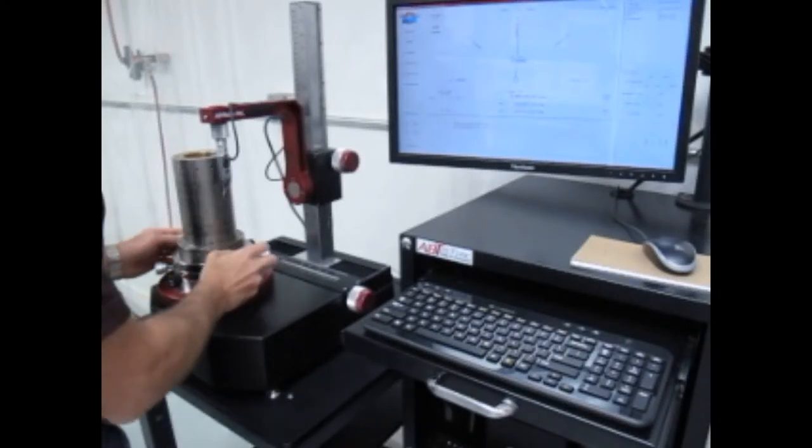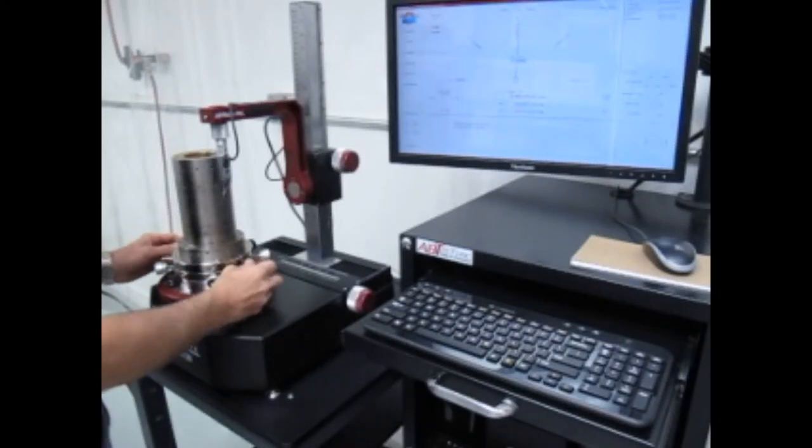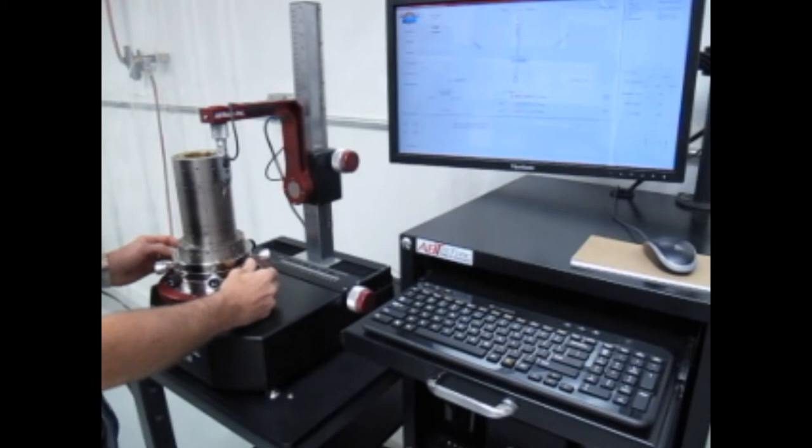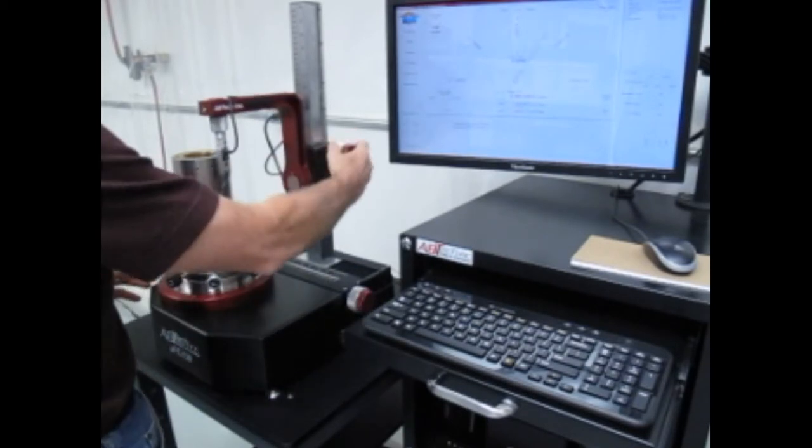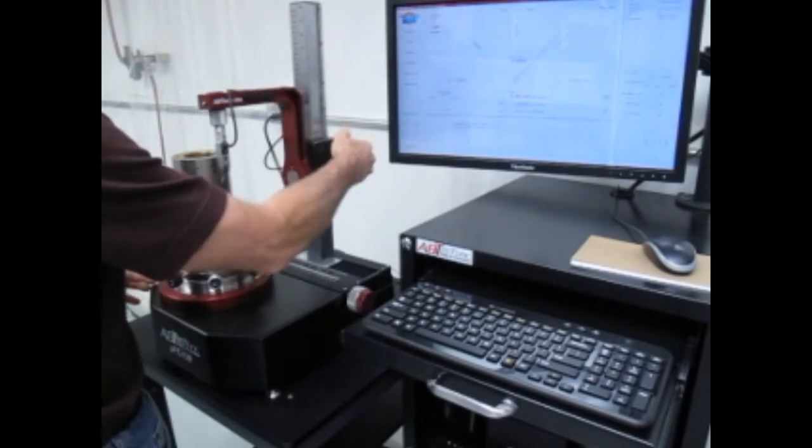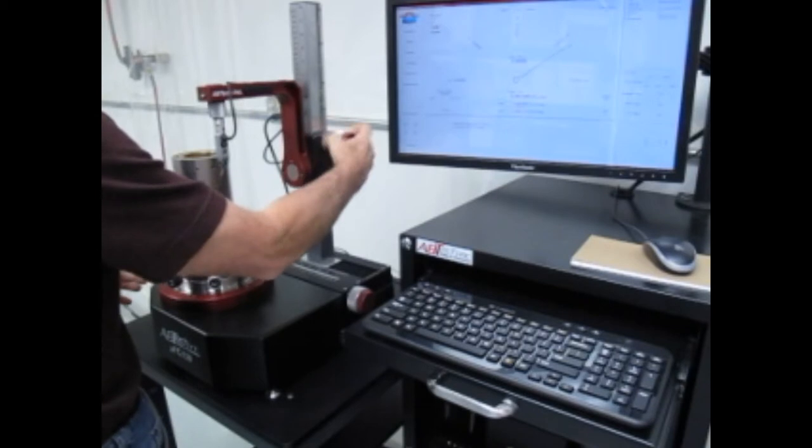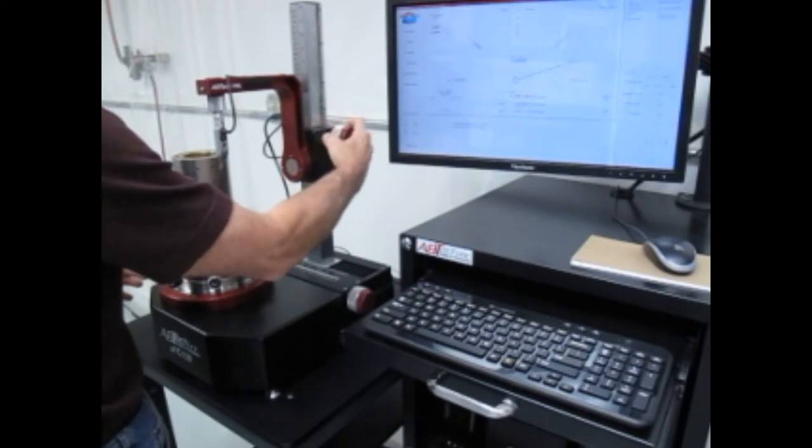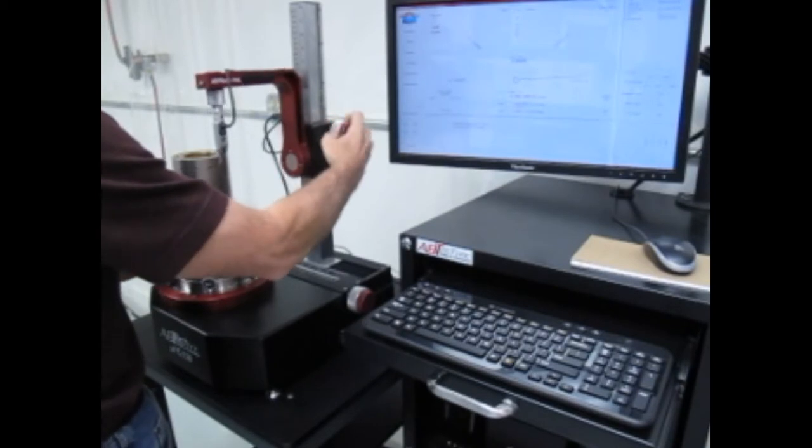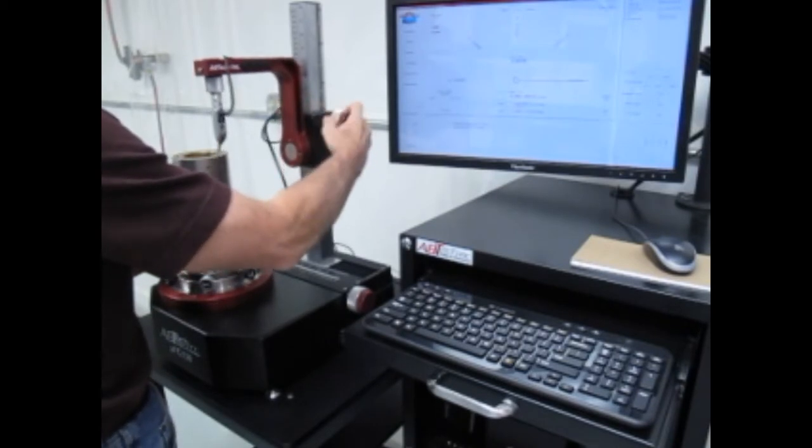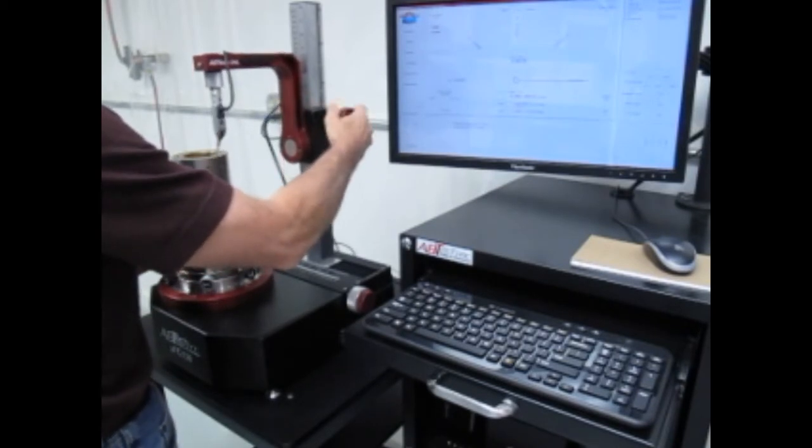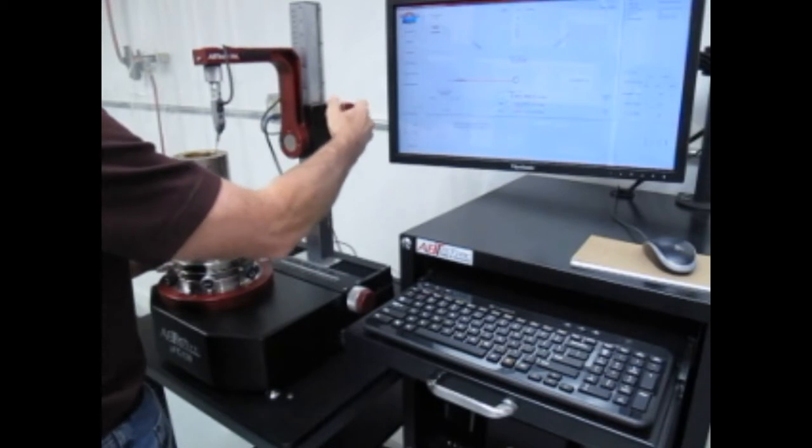Now I'm going to change from a diameter to a face and take a flatness measurement. So I'm going to bring the probe up using the macro knob, which is the clear anodized inner knob, the larger one.